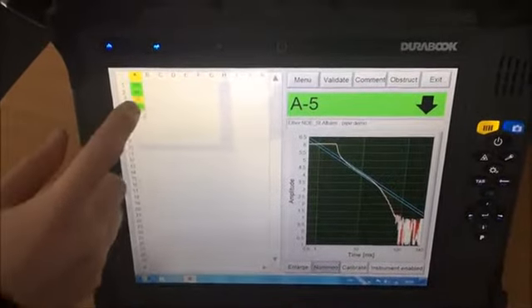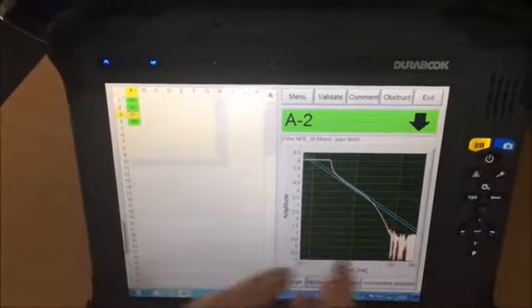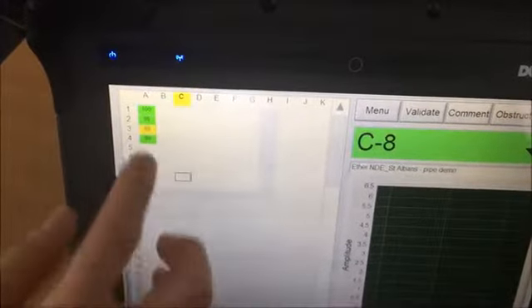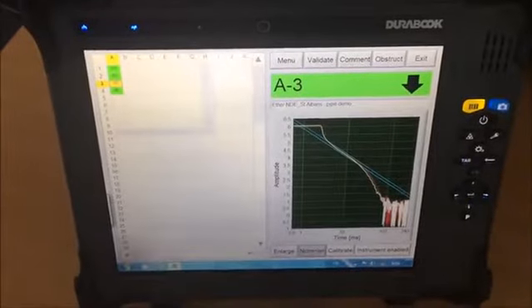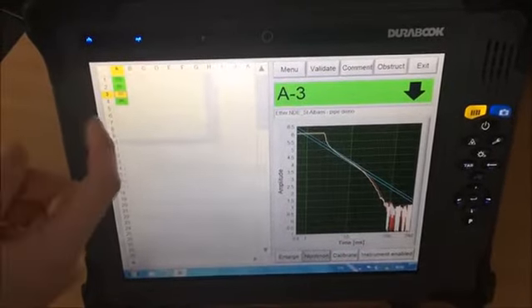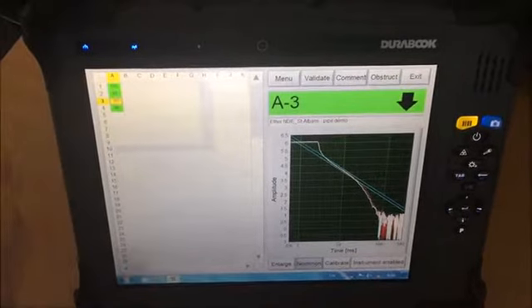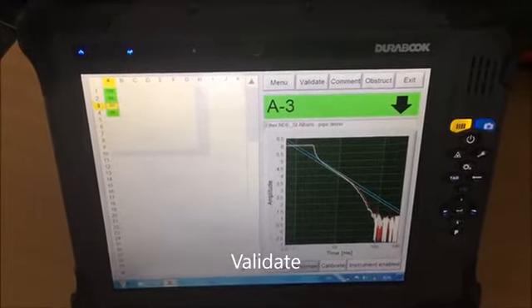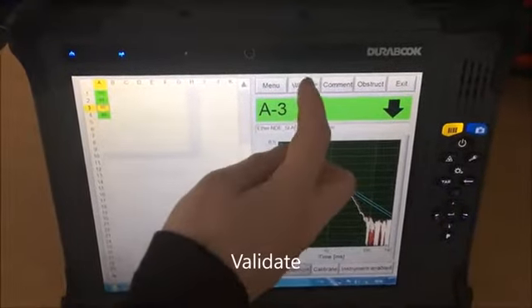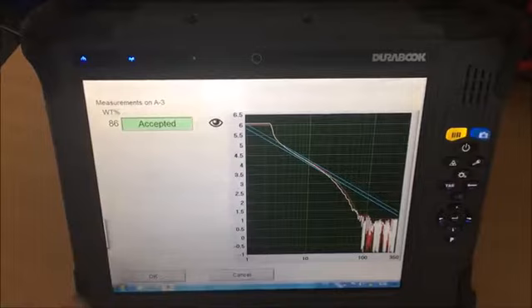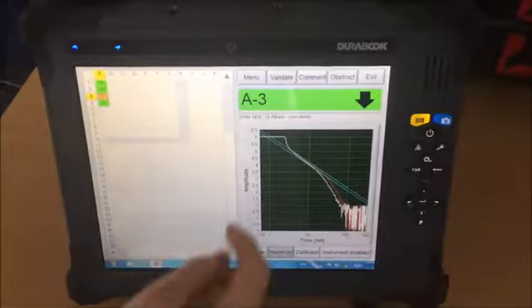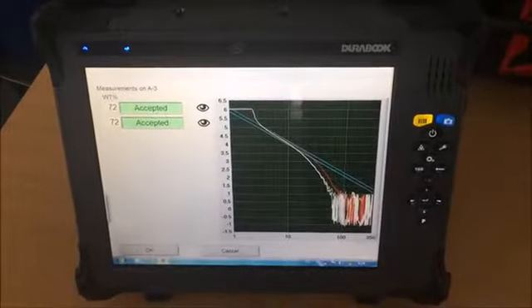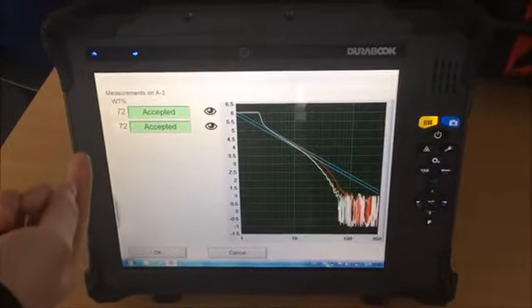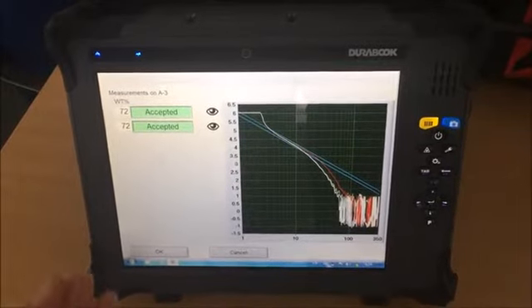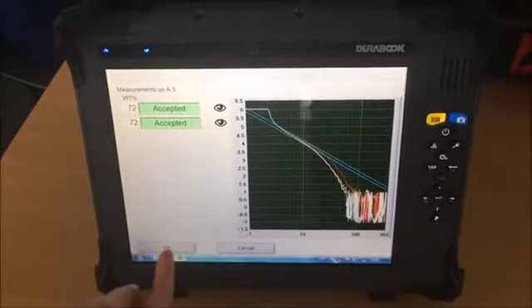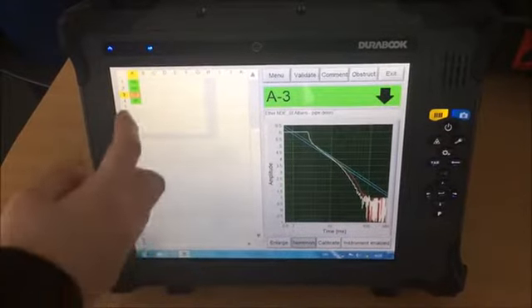Okay. In this case, the third measurement is showing 86% of wall thickness. We need to validate this point because it's more than 10% of the wall thickness, and we can do that by selecting validate. So we can validate now and see that both measurements are within 5%. So the measurement is repeatable. So we can now click OK.